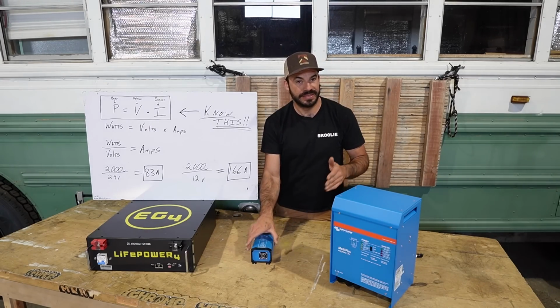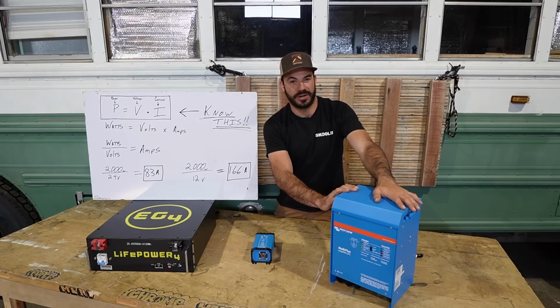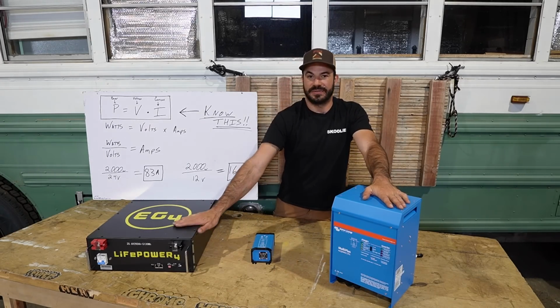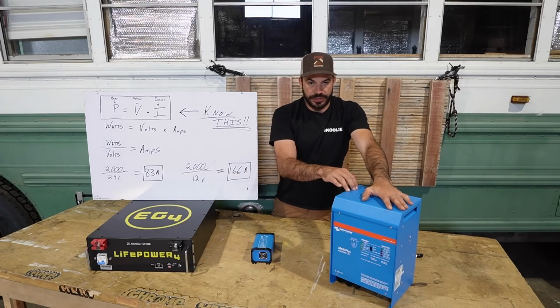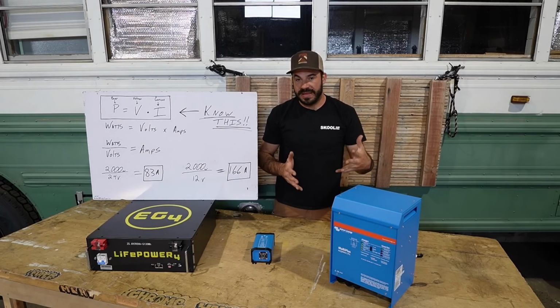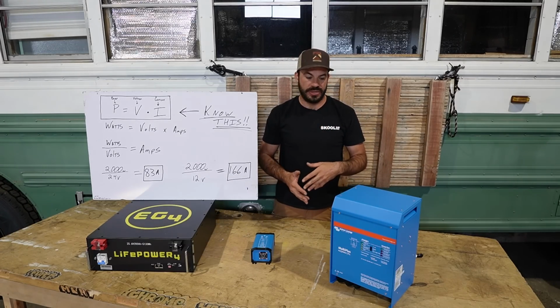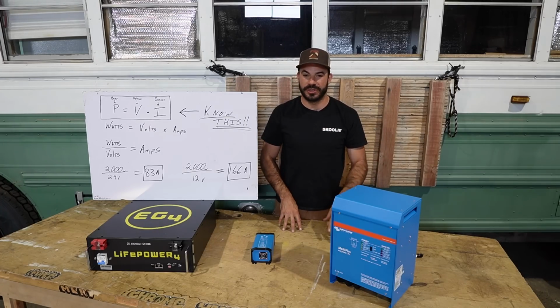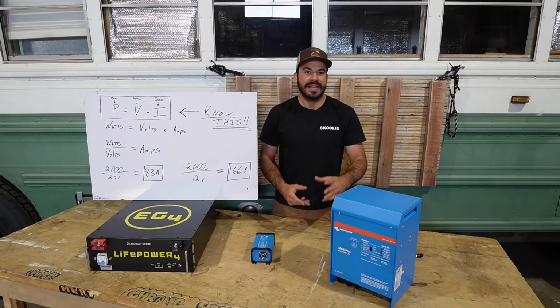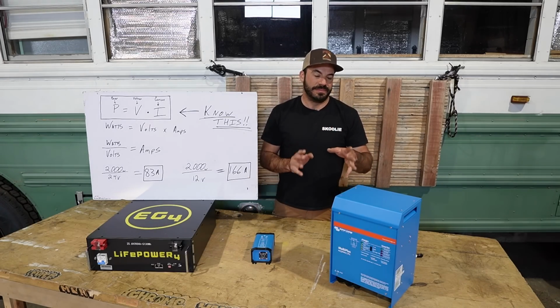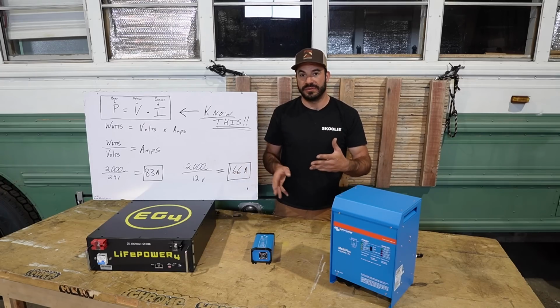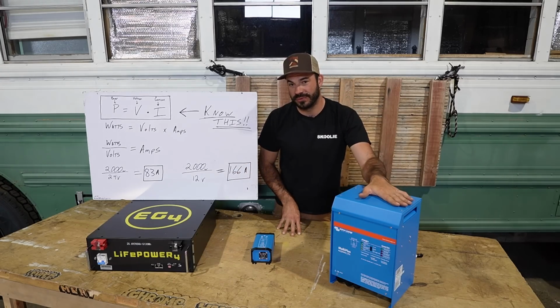And then last, but certainly not least, the most expensive part of this whole project, well maybe aside from the batteries, is the inverter. Now the inverter always has to match your battery's voltage. You can't run a 24 volt inverter on a 12 volt battery system and vice versa. You have to match the two, and so since we're going to a 24 volt battery, that means we need a 24 volt inverter.